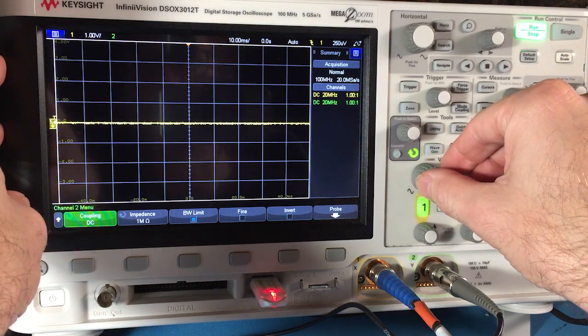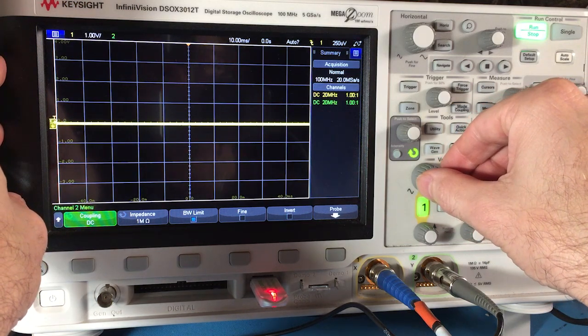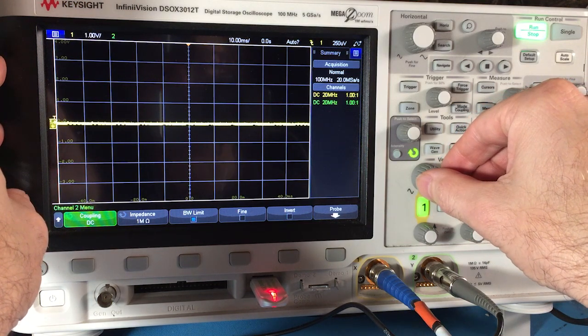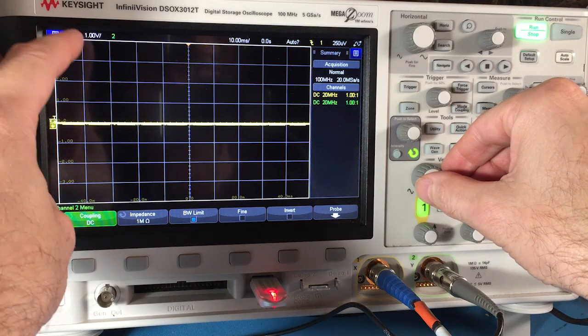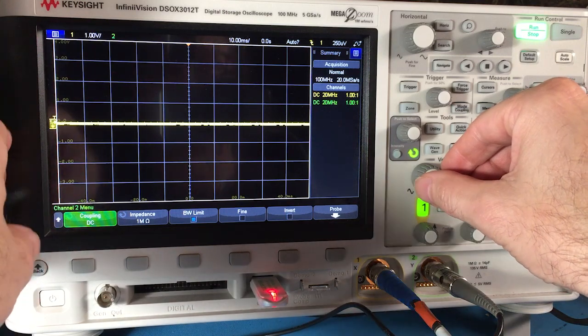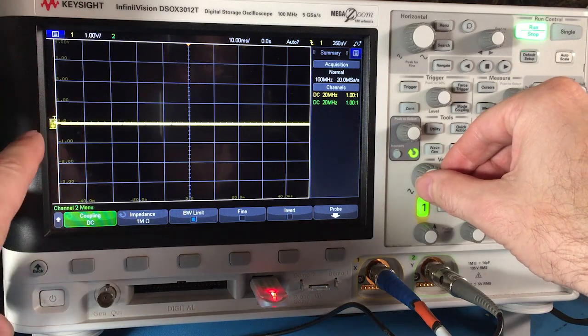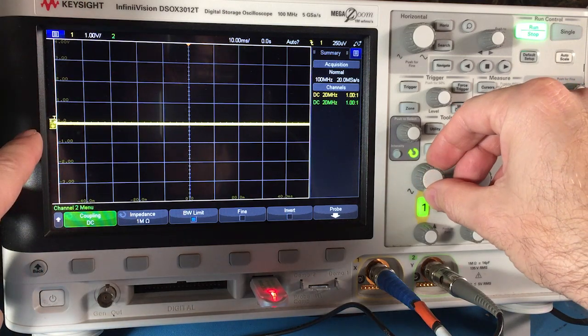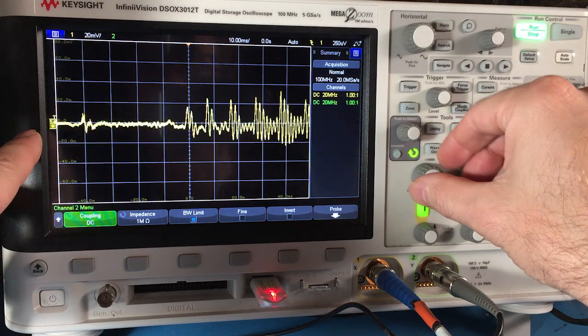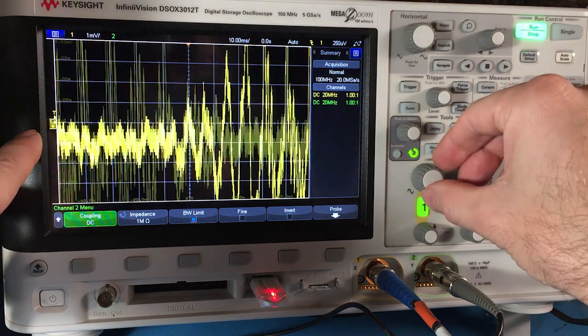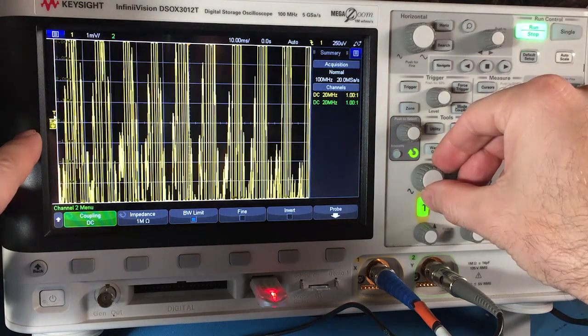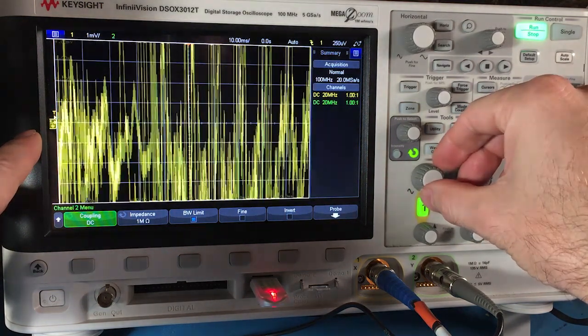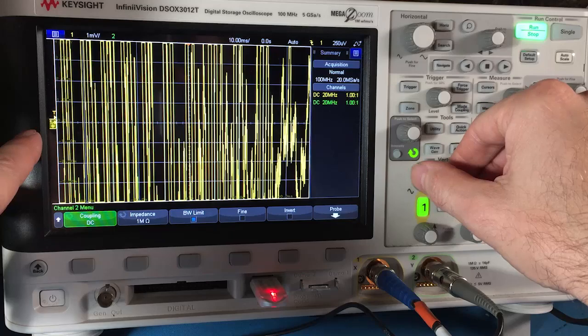So obviously if I was trying to see what was going on in the signal, being on one volt per division might be a bad setting because I could barely see anything. Then the same point, if I had on one millivolt, that's also just jumble too.